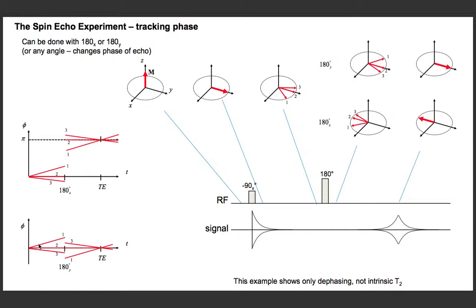As they all have an off resonance, which is linear, the phase increases linearly with time, and that's the slope of those curves. And the times where all those coherences come back together and the net phase is 0 is when you have coherence and form your echo.